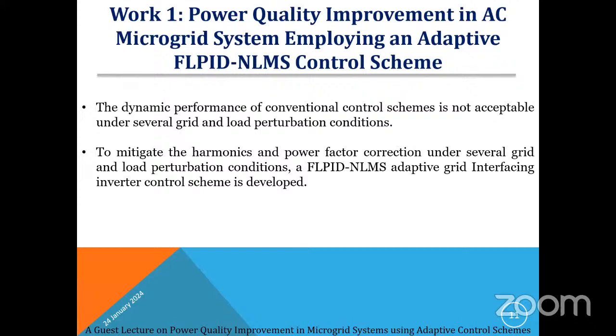Why are you using fuzzy logic? Based on the error change, the fuzzy logic controller will calculate the Kp, Ki, Kd values adaptively based on the DC bus voltage variation. If the voltage is increased at the DC bus side, the fuzzy logic PID controller can calculate the Kp, Kd values based on the grid voltage. If the grid voltage is varying, the fuzzy logic will calculate the Kp, Kd adaptively. That is the reason this control scheme is called an adaptive control scheme.